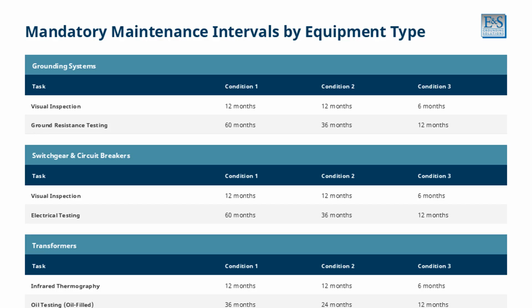For switchgear and circuit breakers, visual inspection follows the same 12-month and 6-month pattern, while electrical testing requires 60, 36, and 12 months respectively. For transformers, infrared thermography requires 12-month and 6-month intervals, while oil testing for oil-filled units requires 36, 24, and 12 months. An important note: manufacturer recommendations take precedence over Table 9.2.2 intervals.